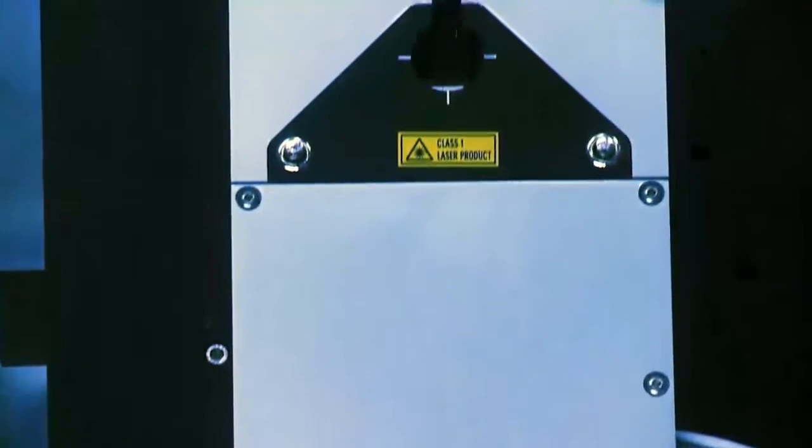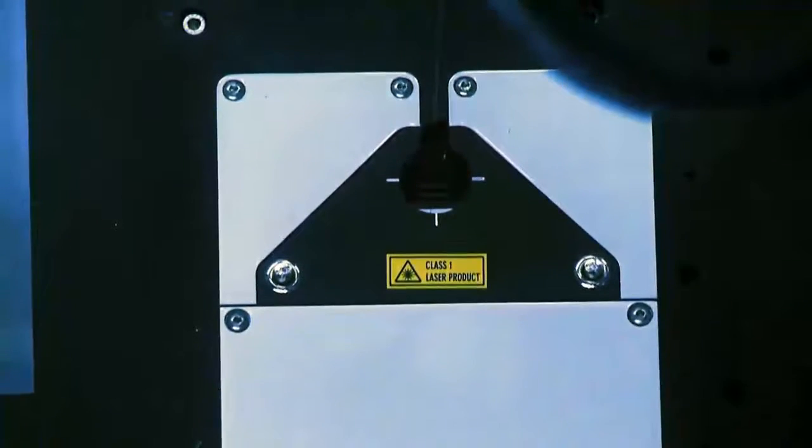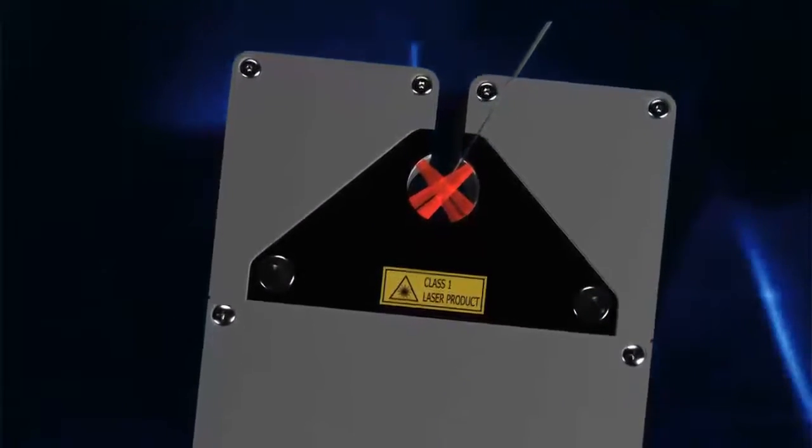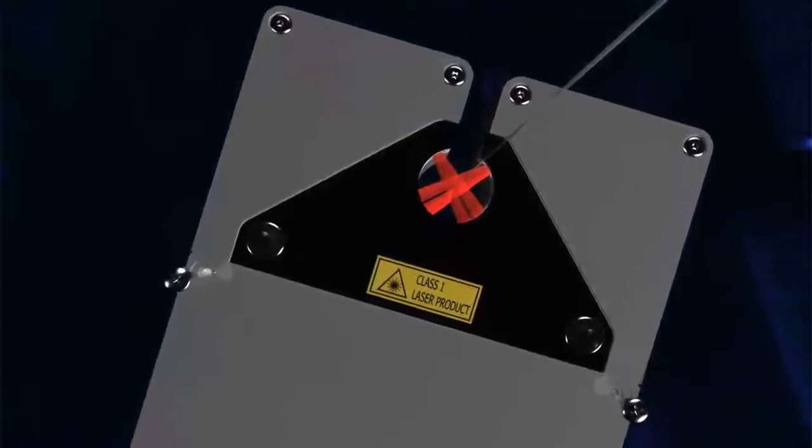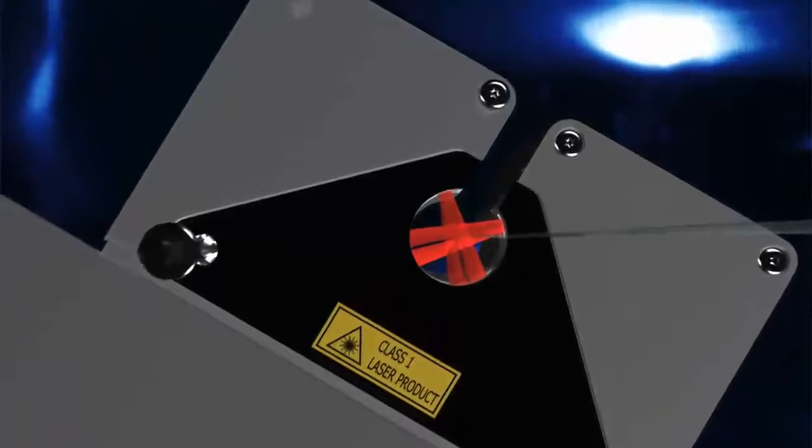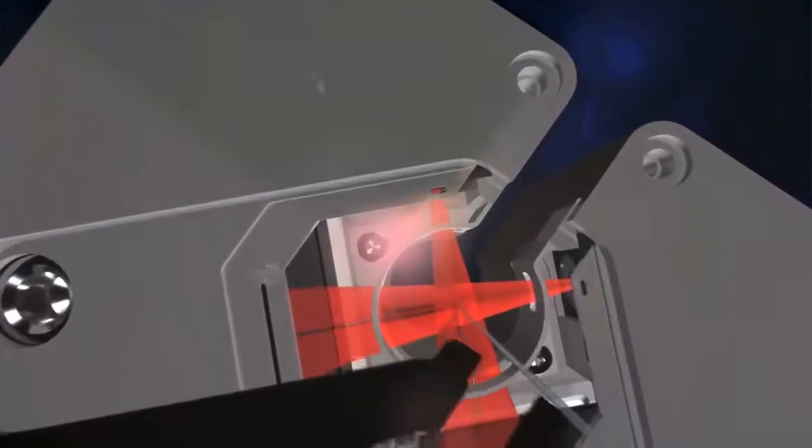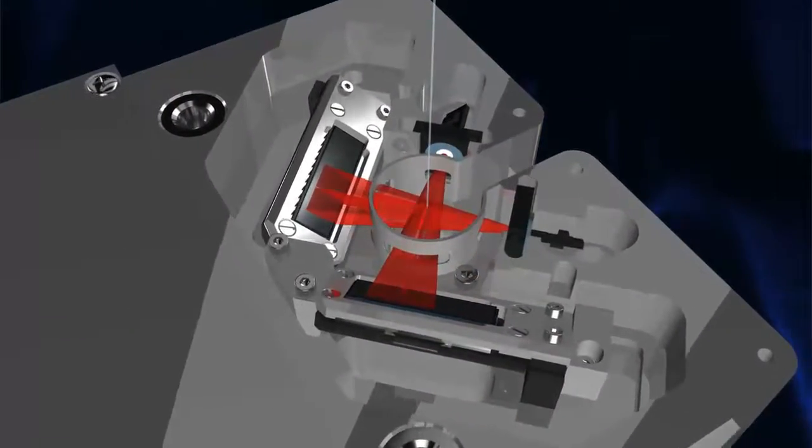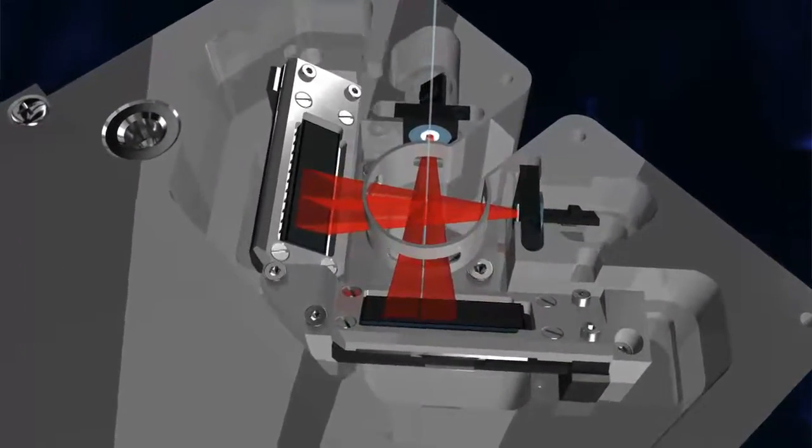The Fibre Laser 6003 is an innovative device for diameter measurement of bare and coated optical fibers from 50 to 500 micrometers. The measuring principle is based on diffraction analysis. The technology utilizes modern CCD line sensors combined with laser diodes as light sources and an intelligent, powerful software.